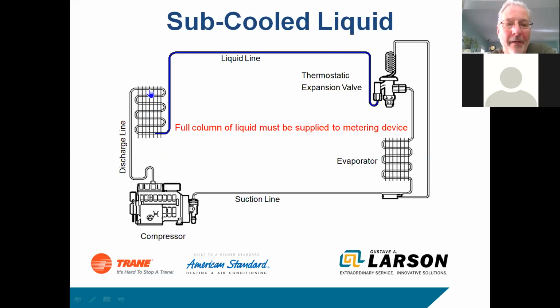If I have a flooded condenser, that's going to mean this pressure is going to be higher. The compressor is going to be working harder. It's going to be costing our consumer more energy at that point. So a sight glass is okay to tell whether or not there's liquid here, but it really is not a good way to charge a system. Do it by subcool. 10 degrees subcool means you've got a properly charged system.